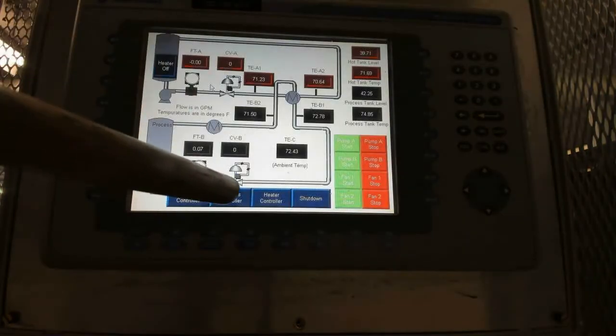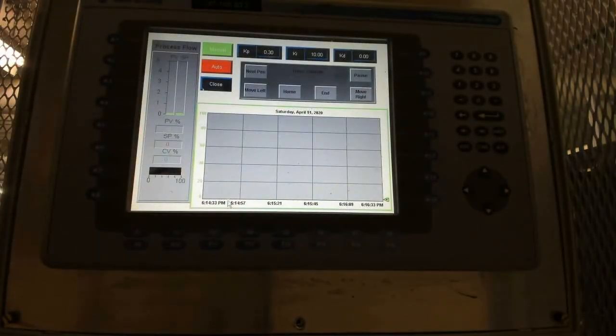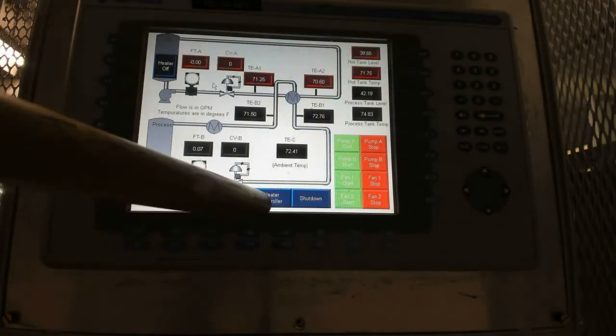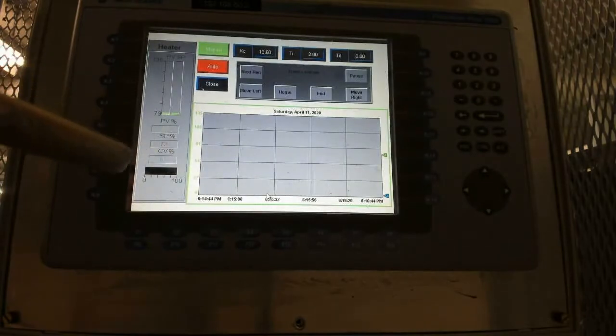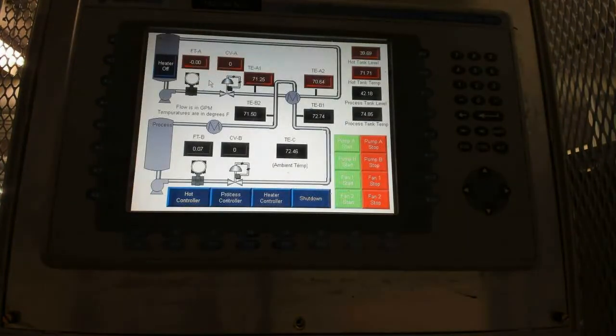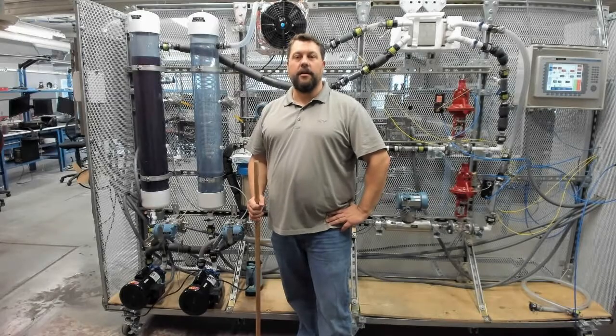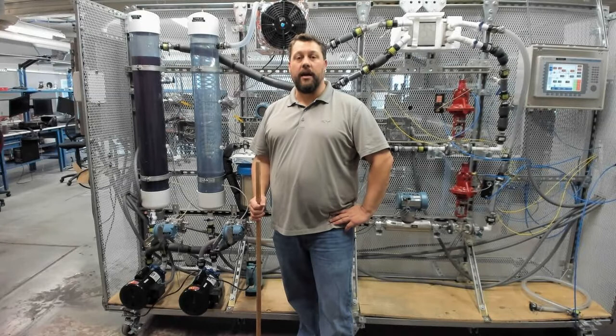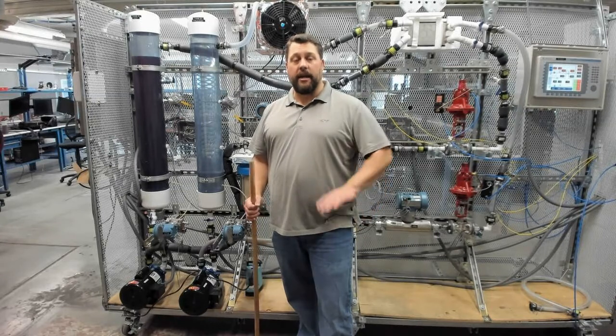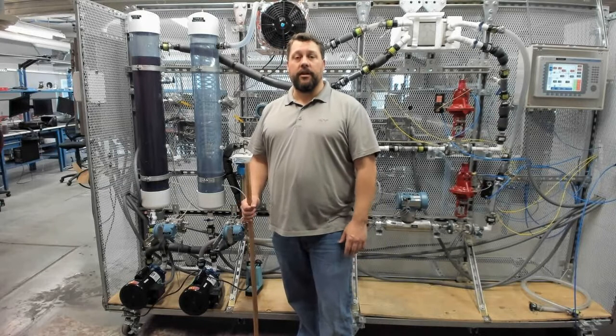Okay, and we can go to the same thing here. We can go into the process flow, so we can adjust the flow rate for the process loop. We can go into the heater control, and this controls how hot we're trying to have that heat transfer fluid, so it'll adjust that as well. And we'll take a closer look at those parameters in future videos. It might be helpful to have your piping and instrument diagram and the ladder diagram set on the side while we trace out the system here.